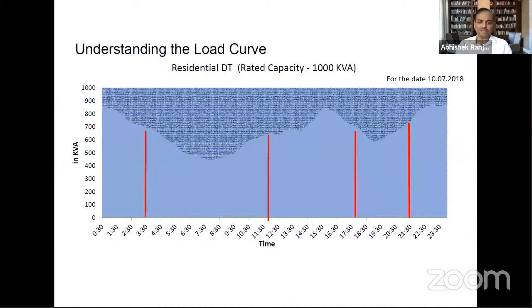Now this is at the distribution transformer level. The load curve of a residential DT shows very high daily variation. From this 1000 kVA DT, it ranges from 900 to almost 450 kVA, the daily diurnal variation.